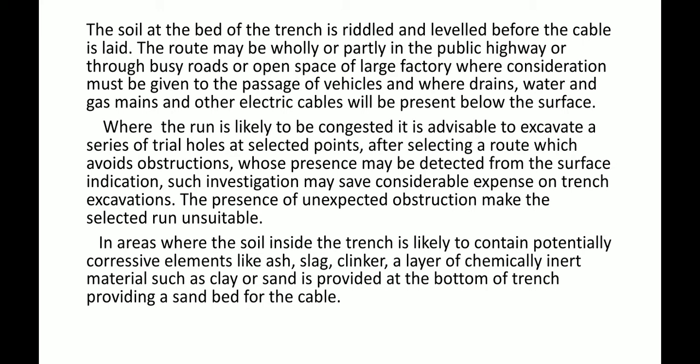The presence of unexpected obstructions may make the selected run unsuitable. In areas where the soil inside the trench is likely to contain potentially corrosive elements such as ash, slag, or clinkers, a layer of chemically inert material such as clay or sand should be provided at the bottom of the trench.